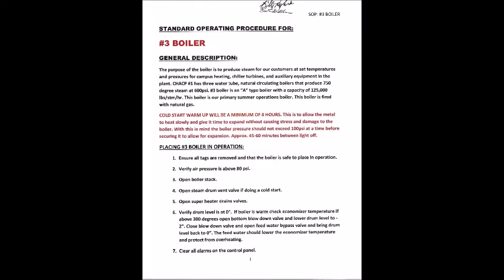The purpose of the boiler is to produce steam for our customers at set temperatures and pressures for campus heating, chiller turbines, and auxiliary equipment in the plant. CHACP number 1 has 3 water tube natural circulating boilers that produce 750 degree steam at 600 psi. Number 3 boiler is an A-type boiler with a capacity of 125,000 pounds of steam per hour. This boiler is our primary summer operations boiler. It is fired with natural gas.